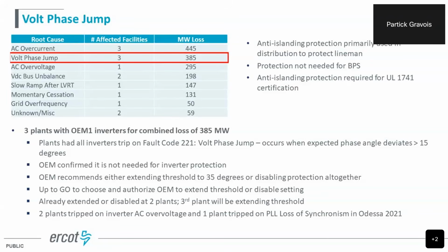So out of the 3 plants, 2 of them have already, one has extended the threshold, one has disabled, and the 3rd plant will be extending that threshold within the next month. Out of these 3 plants, 2 of the plants tripped on AC overvoltage last year. They had not mitigated that. They were still in the process of mitigating that, but then they tripped on a different root cause this year. And again, one of those was a PLL loss of synchronism that disabled, and this time they tripped on the volt phase jump instead. So kind of a similar root cause here.